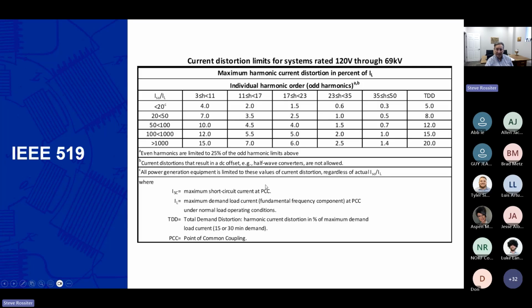And what IEEE 519 says is, depending on how large of a customer you are or how you compare to the source capability of the utility, which they look at as ISC, or the short circuit at the common coupling where the utility connects to you, compared to the IL, the load, how large you are. So if you have a utility that has 100,000 amps short circuit ability, and you are 1,000 amps of that 100,000 short circuit, you're going to come into the chart here at 100, which should be somewhere in this area here, and they're going to say, all right, we're going to allow you to have 12% total demand distortion.